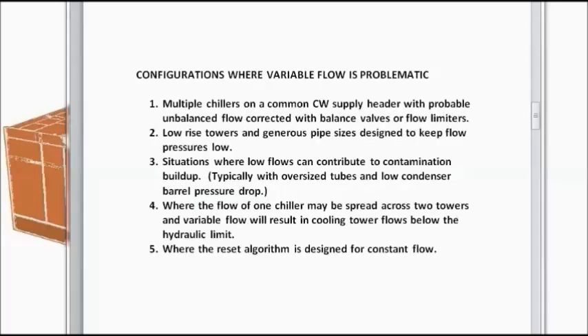Now here is a list where variable flow is problematic with the following configurations and situations. Number one is where you've got multiple chillers on a common condenser water supply header, and it is necessary to balance the flow to each chiller with valves or flow limiters.